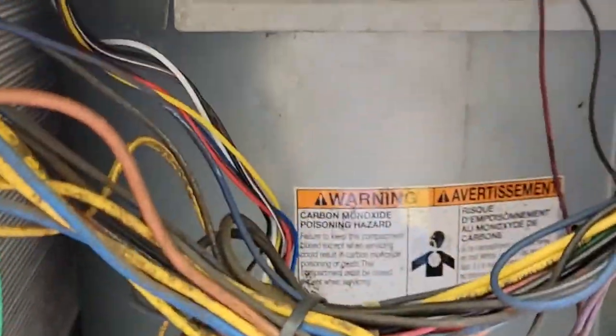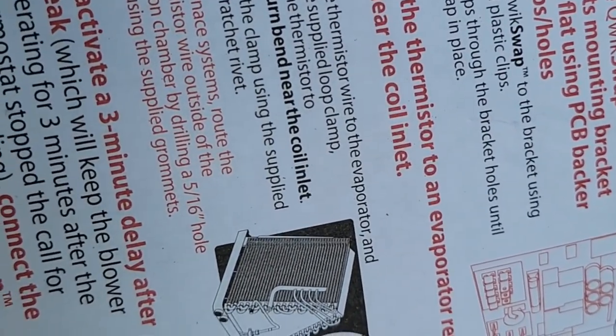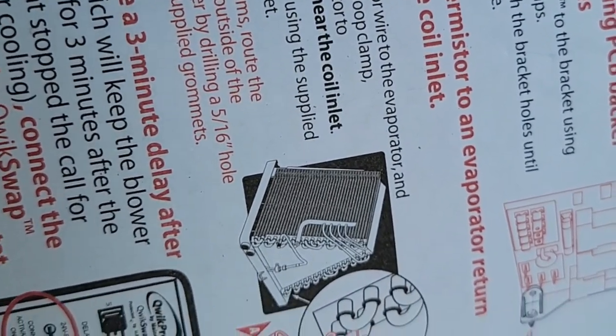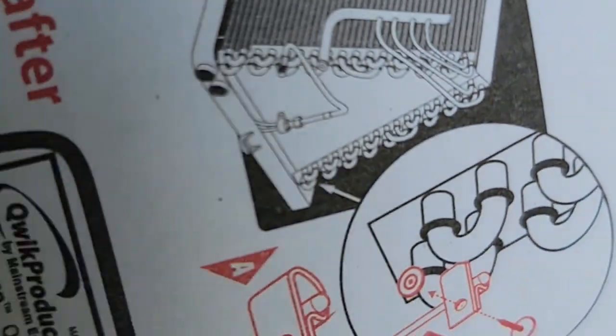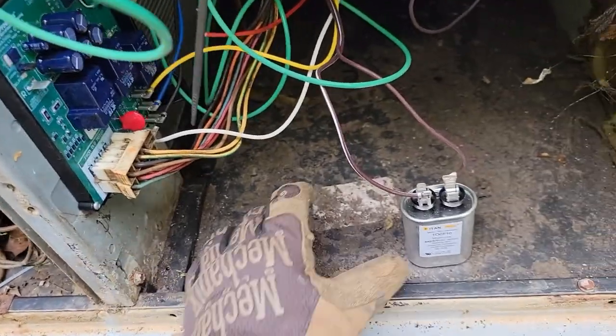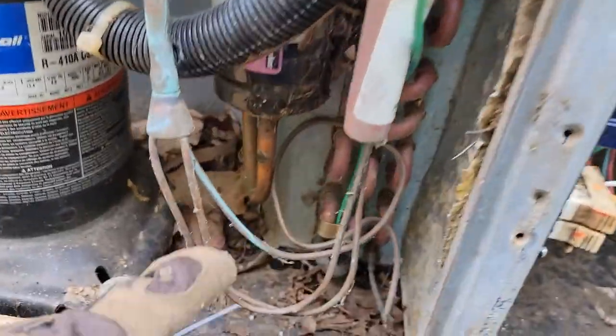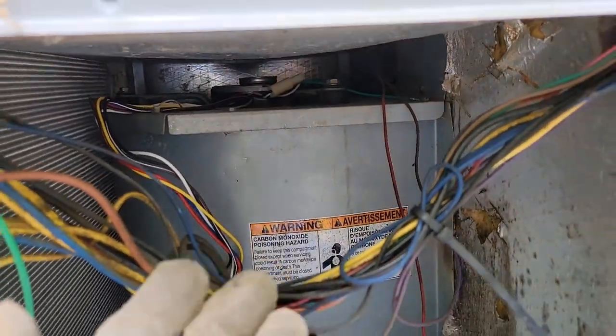I'll go ahead and get this mounted and then turn it on so you can see it working. After you mount the QwikSwap board, you attach the thermistor to the evaporator return bend near the coil inlet — see the picture right there. Please read the instructions. The board is mounted; now all I've got to do is mount my capacitor for the PSC fan and I've got the thermistor and clamp installed on the U-bend.